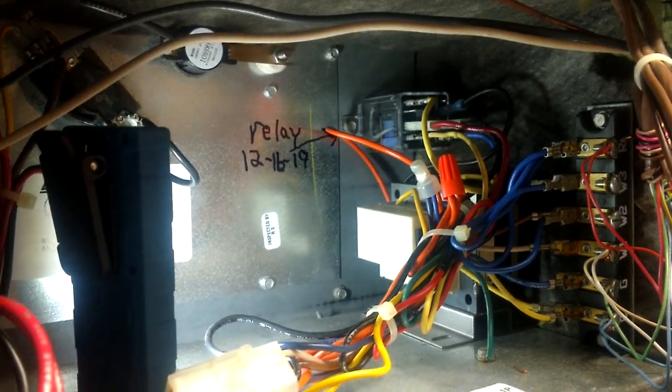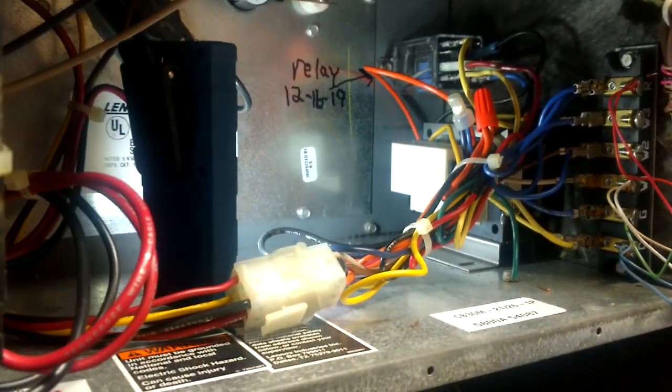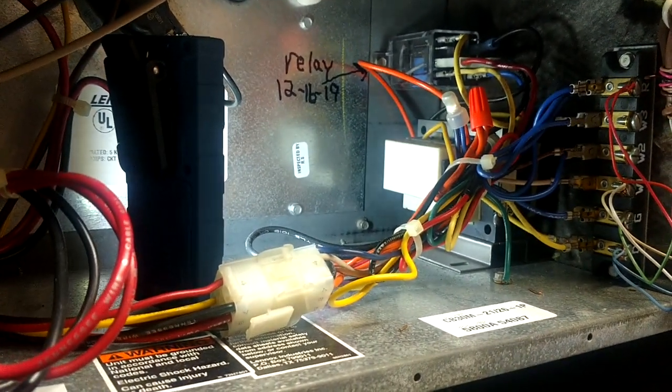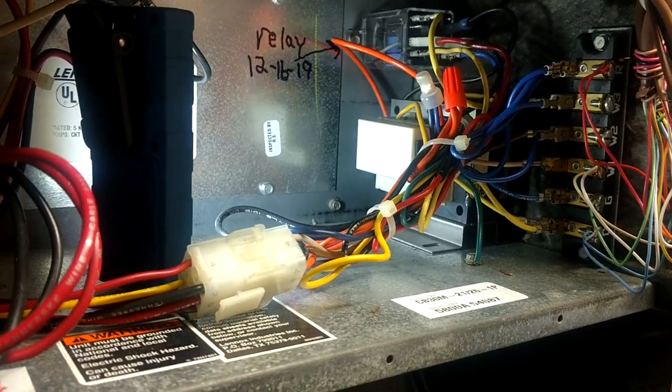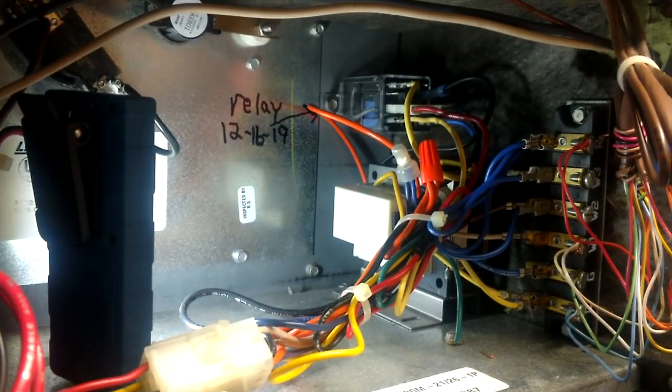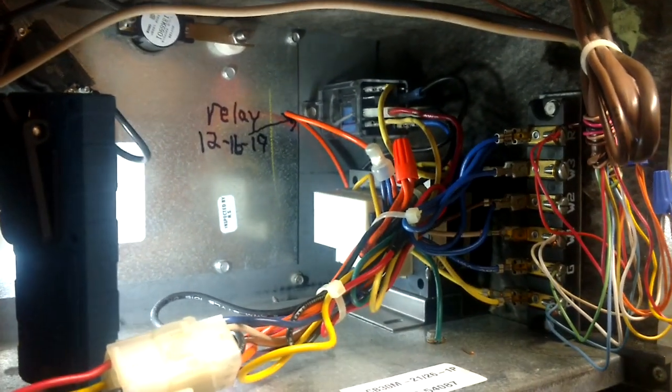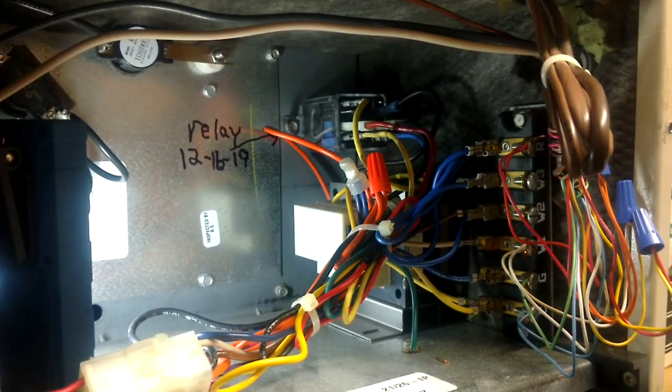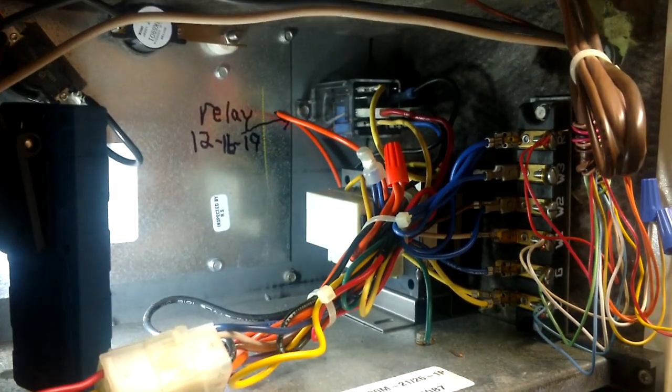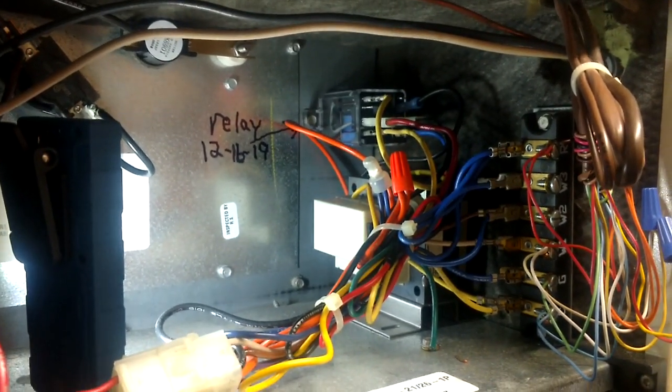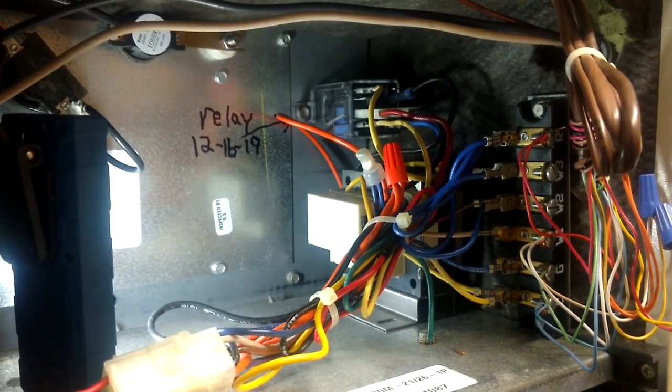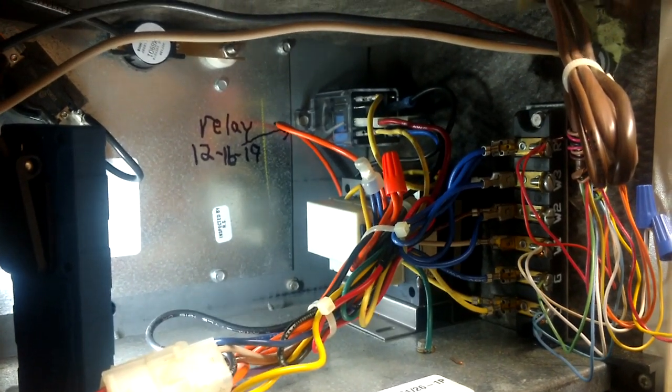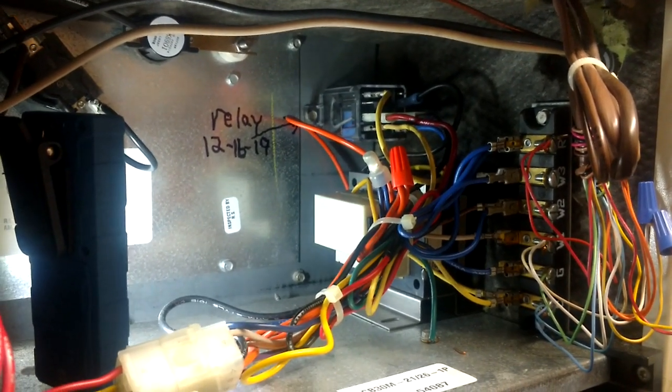You'll go over there like a big shot and flip your fan to on thinking you've got it, and then it don't come on. And you can't figure out why. And you get to looking at the box your relay was in, or you dig your relay out and look on the side of it, and it's a dang high voltage coil. So that mistake has been made by myself more than once.